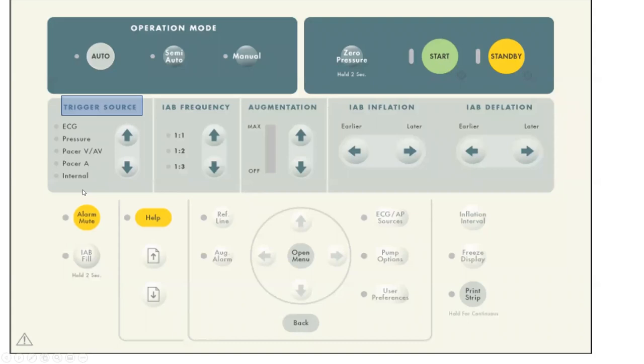However, it can use other triggers that are not advised. It can use the pressure to trigger, meaning it looks at the dicrotic notch and it inflates on top of it, and it deflates just before the arterial pressure rises. However, this should not be used. It's preferred to use EKG because when you use a pressure, the inflation and deflation are timed to the length of the preceding cardiac cycle. So the response to the changes in cardiac cycle in somebody with irregular rhythm is more delayed if you use the arterial waveform, and the balloon may remain inflated between cardiac cycles. So you typically should not use it. You use a pressure for timing adjustment, and the machine does that, and you can do that, as I explained, but you don't use it to trigger.